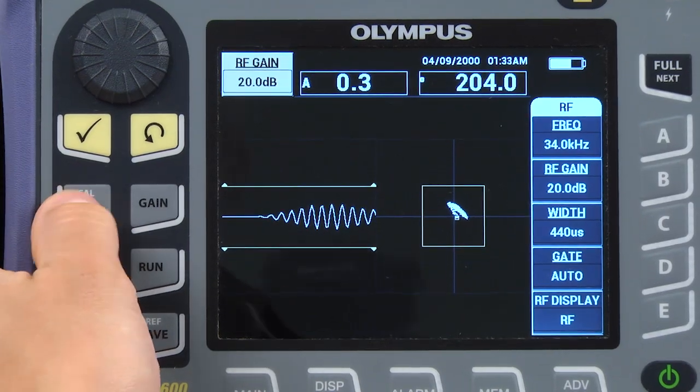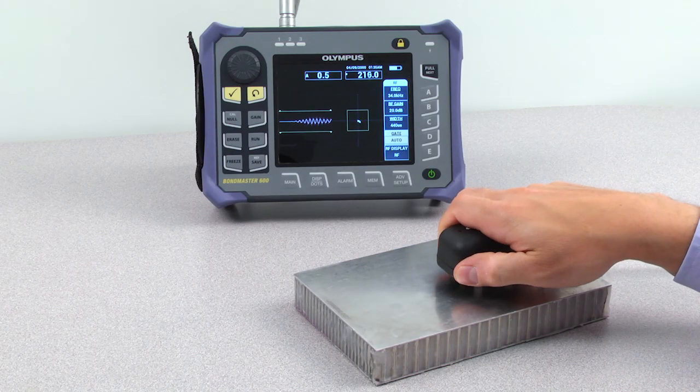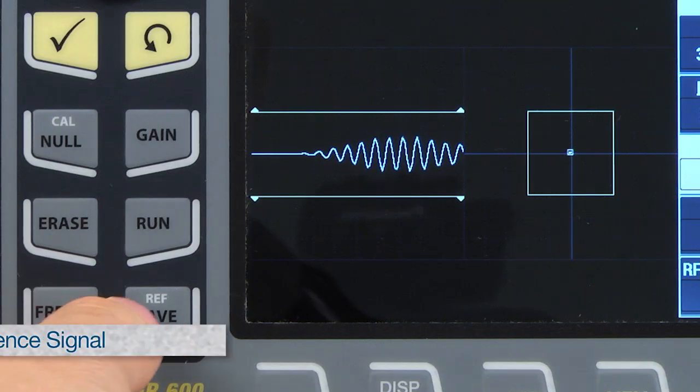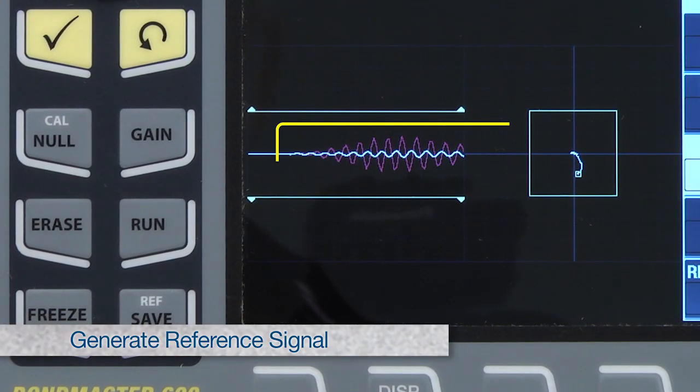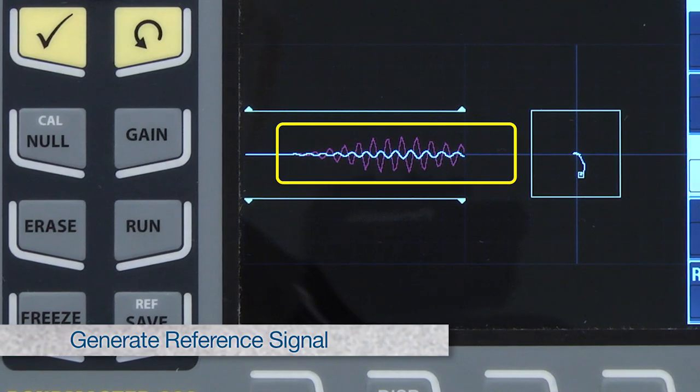Press the NULL key while keeping the probe on a defect-free area. Press and hold the SAVE key until a short beep is heard. The signal will be displayed in the background. This is the reference signal.